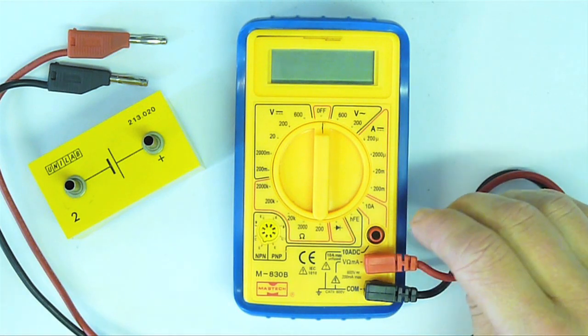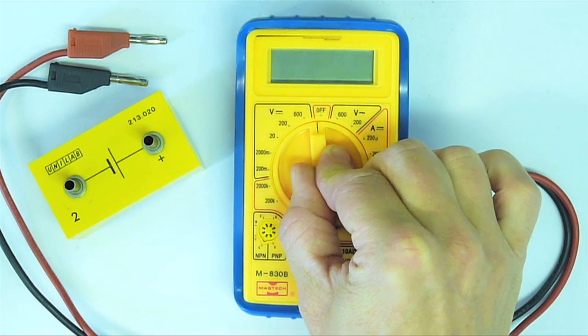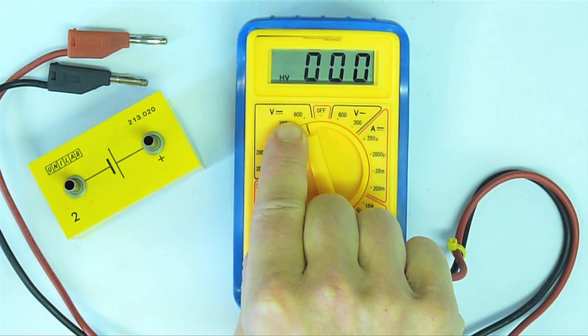To measure an unknown voltage, I always start off on the large range. This range here says 600, 600 volts. That's the full scale deflection. That means the largest voltage that the instrument will read on this range.